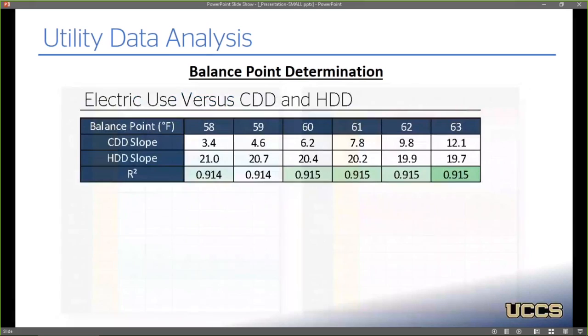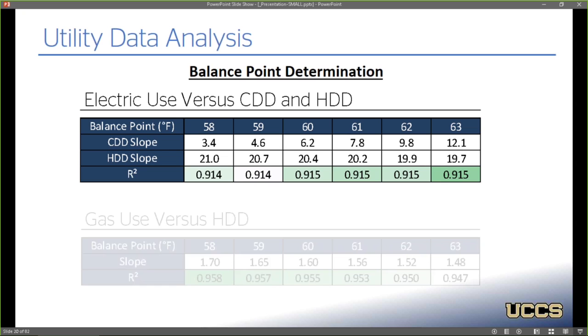Running a regression against each of those balance points on the electric side, you can see I have a cooling and a heating degree day slope, because this is a multivariable regression analysis and the electric use will be dependent on both. But you can see my R squareds are all really good. They're all above 0.9, but they tend to be the best around the 60 to 65 balance point range.